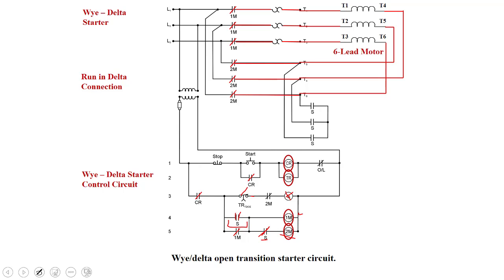Now what do we have? Well, we have the windings connected up in delta. Let me give you an example here. If this is big A, this side is little a. So big A, little a, big B, little b, big C, little c. We can follow it through. Little a goes to big B. Little b goes to big C. And little c here goes back to big A. So we're in delta, and that's the run. We're going to run in delta. Press the stop button and everything will de-energize. So that's our Y delta starter.